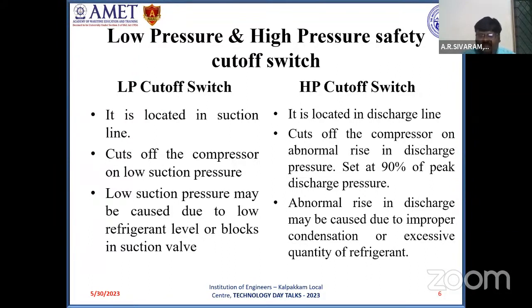So, a possible cause for abnormal rise in discharge pressure is improper condensation. That is, when the condenser is not functioning normally, it can result in an abnormal rise in discharge pressure, which can result in tripping of the compressor. We would have seen split type air conditioning systems, which have two units. One is the indoor unit, that is the evaporator part, and the other is the outdoor unit, which has the compressor and condenser. Split type systems normally employ an air-cooled condenser in the outdoor unit. The fan in the air-cooled condenser provides the air. If the fan in the condenser is not rotating or not working, we will not get liquid refrigerant at the condenser outlet, and we will not see any obvious sign of malfunction in the condenser. Instead, what is likely to happen is that the discharge pressure, or compressor outlet pressure, will abnormally increase, which can result in the tripping of the compressor.